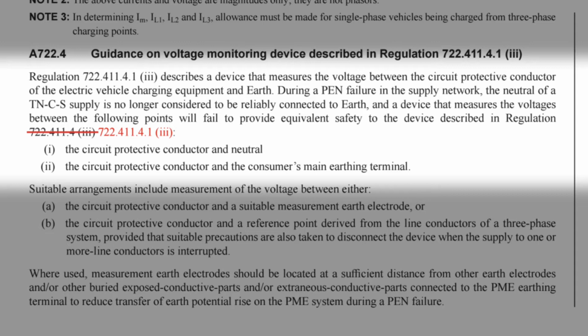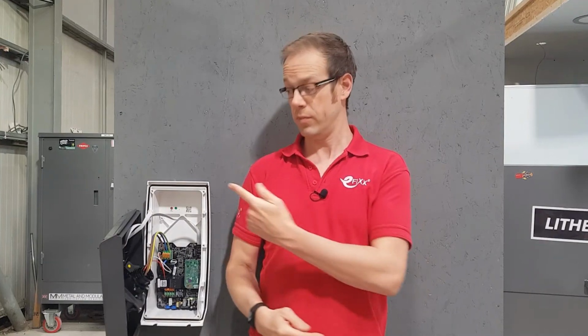722.411.4.1 indent 3. Indent 1, the circuit protective conductor and neutral. Indent 2, the circuit protective conductor and the consumer's main earthing terminal. So this monitoring device can't just be connected across the conductors mentioned in those two indents there, as it wouldn't reliably measure the voltage from CPC to earth. So what's the solution? Well, let's just have a look at part A of A722.4, as part B is concerned with a three-phase system.